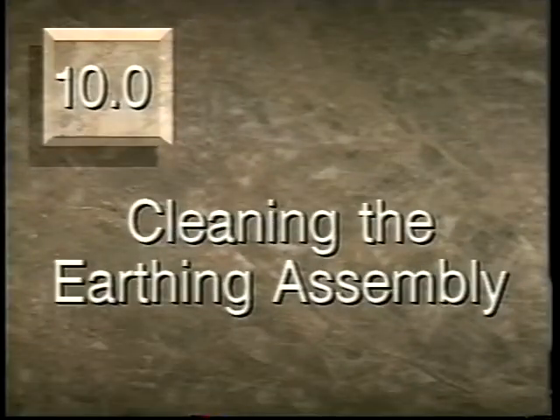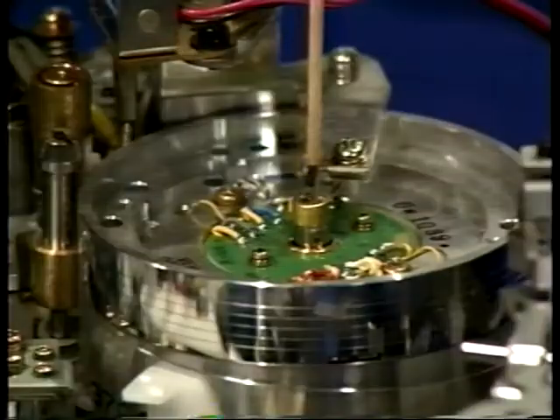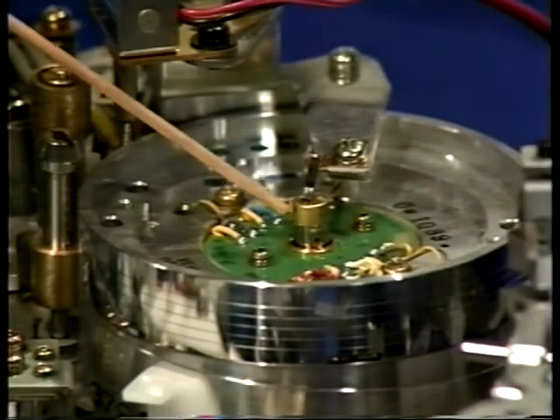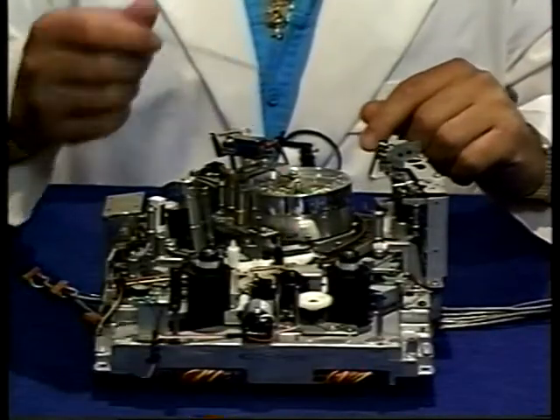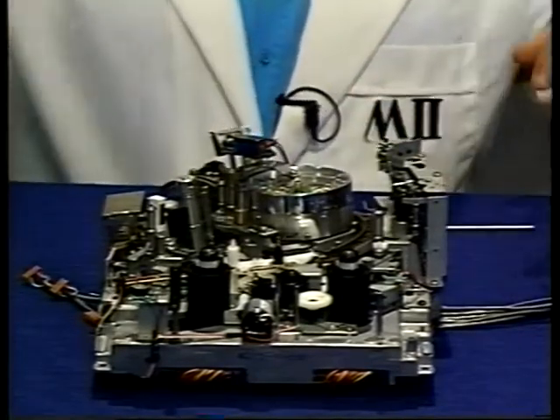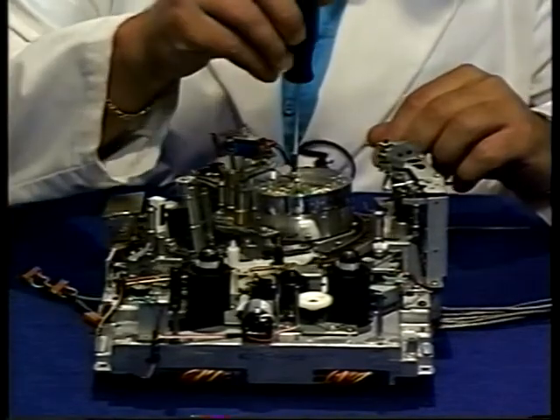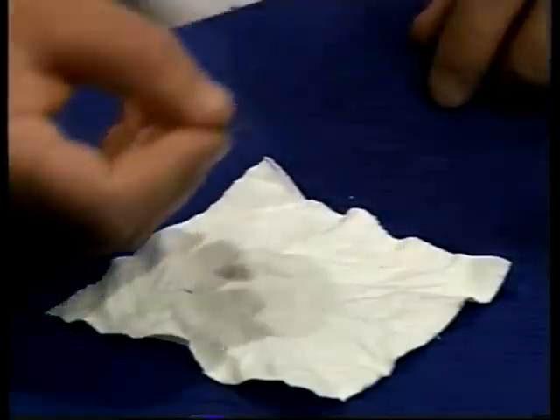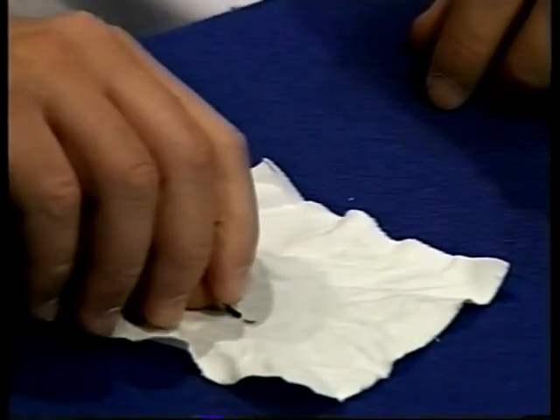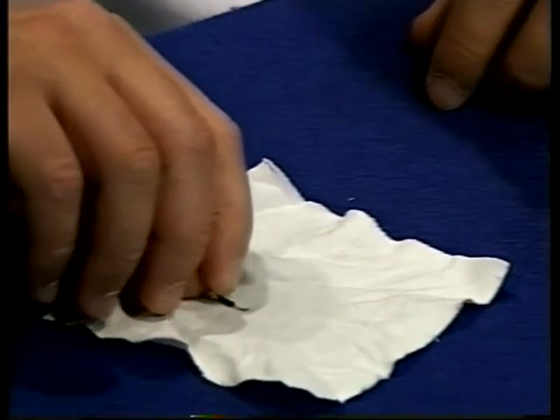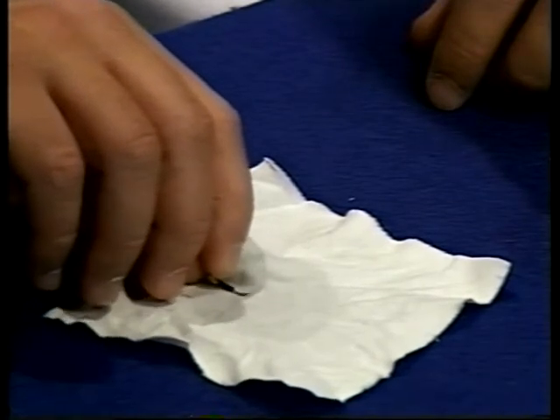Section 10. Cleaning the earthing assembly. The earthing brush is located here, and the slip assembly is located here. The first step in cleaning the earthing assembly is removal of the earthing brush. Clean the contact area of the earthing brush on a pad moistened with alcohol. Rub it on the pad until dirt is removed.